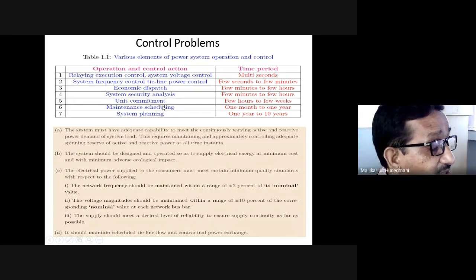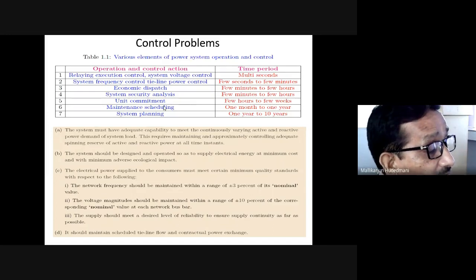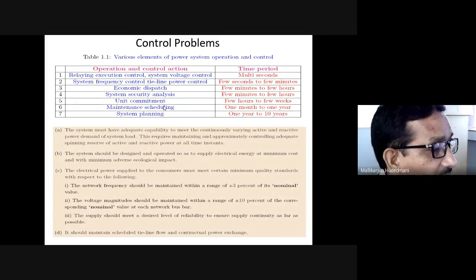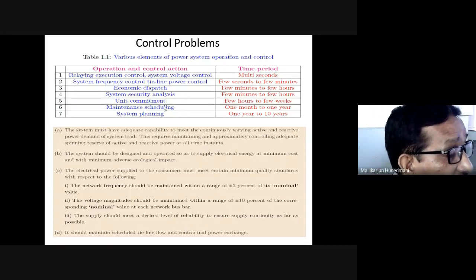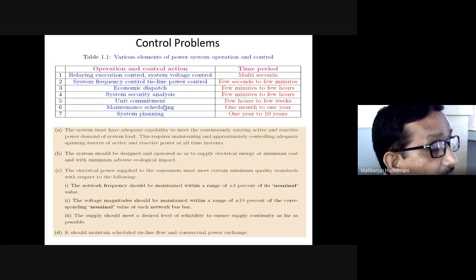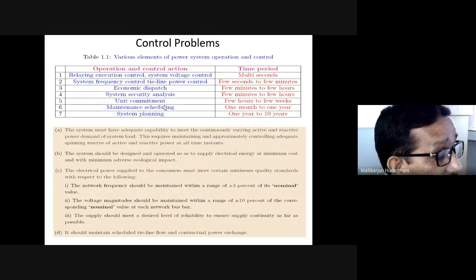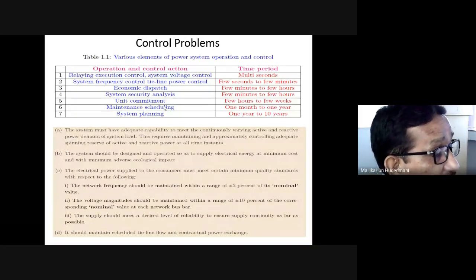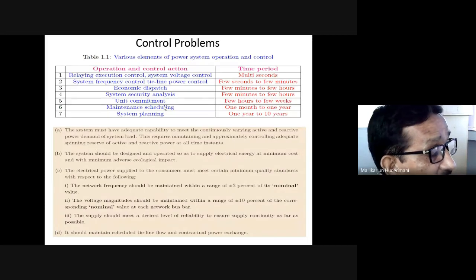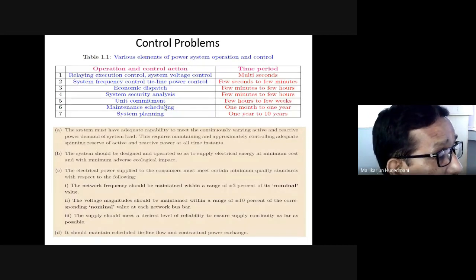The other way is shutdown. When I want to take out a generator, as per the load decline, it is not intelligent to run all the generators all the time. Certain generators need to be withdrawn so that remaining generations meet the requirement. When I remove, which one to remove first, which one second? When I want to add, which one first, which one second? All such commitments, additions, and deletions from the schedule have to be properly planned.